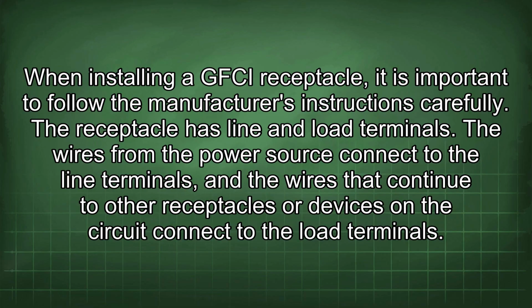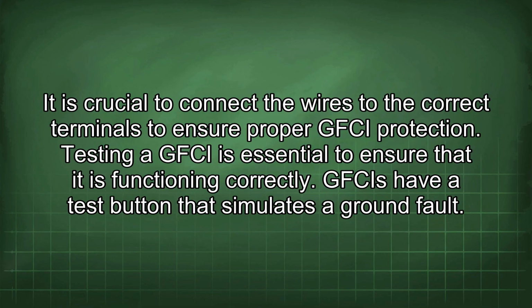When installing a GFCI receptacle, it is important to follow the manufacturer's instructions carefully. The receptacle has line and load terminals. The wires from the power source connect to the line terminals, and the wires that continue to other receptacles or devices on the circuit connect to the load terminals. It is crucial to connect the wires to the correct terminals to ensure proper GFCI protection.